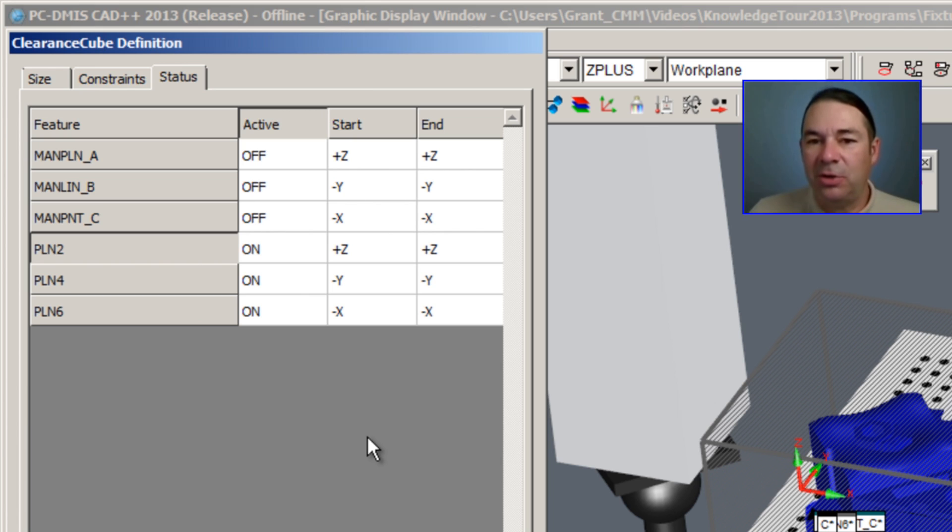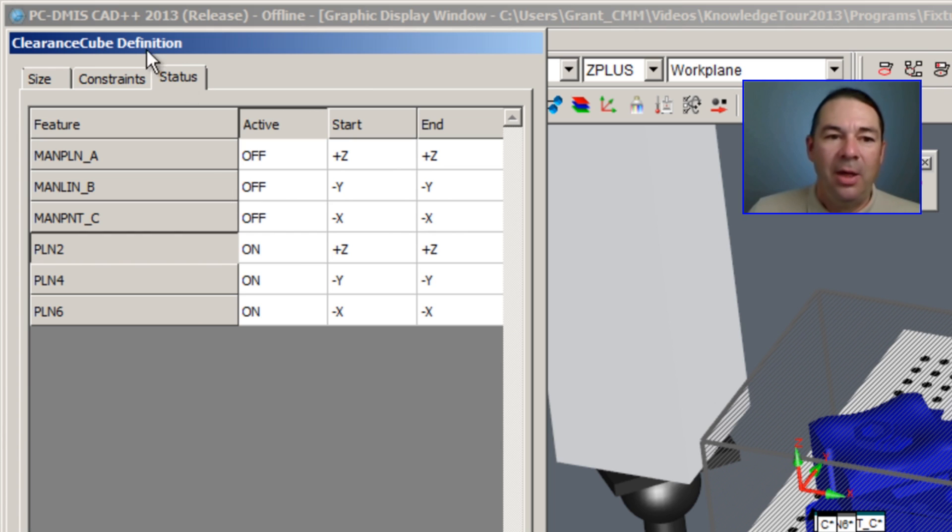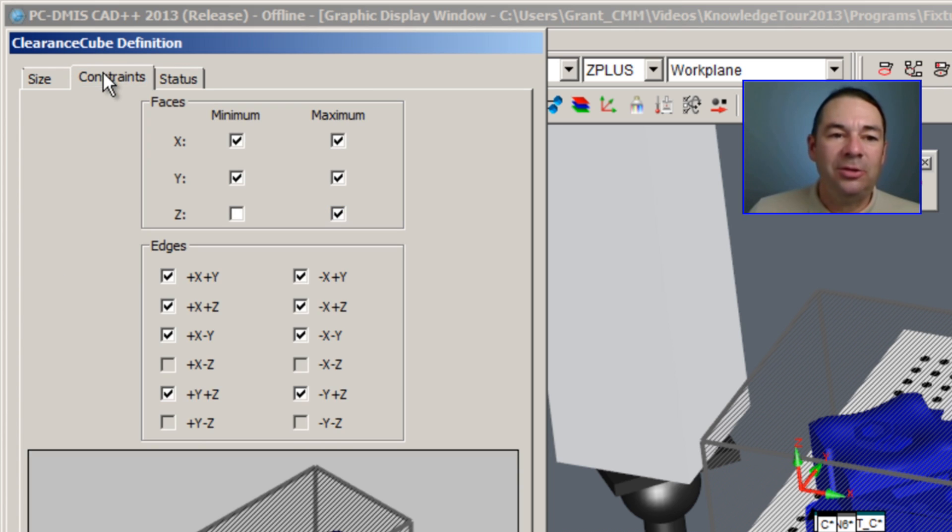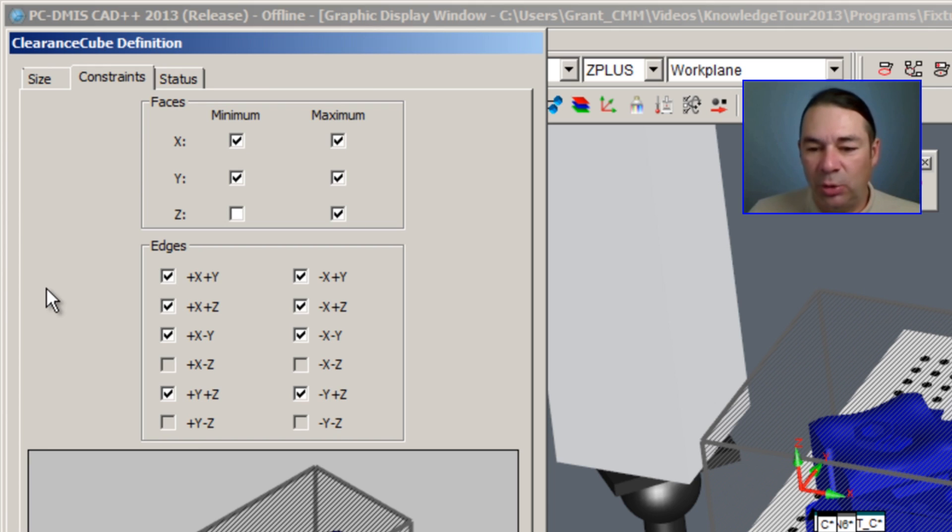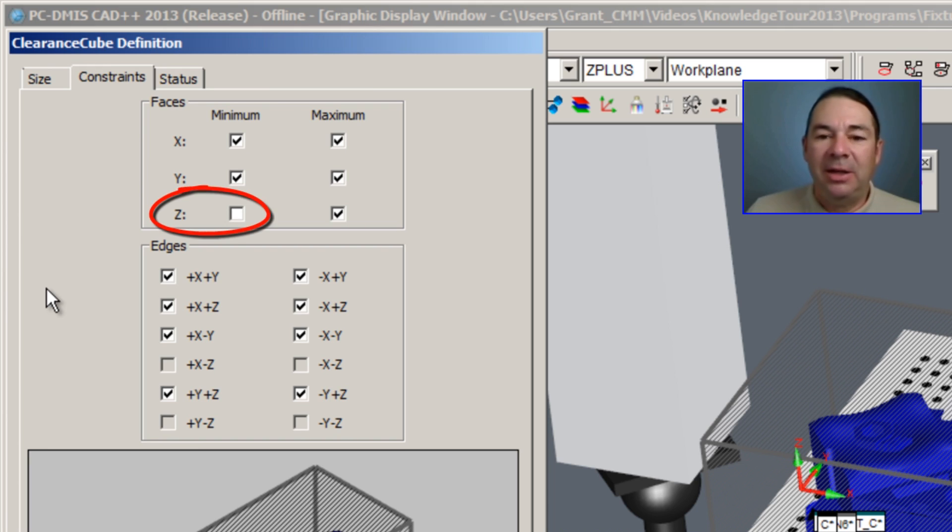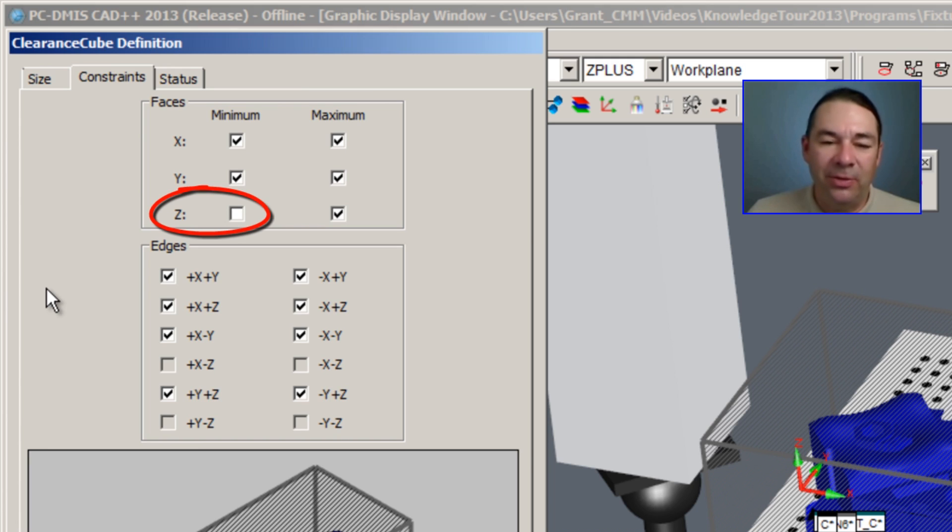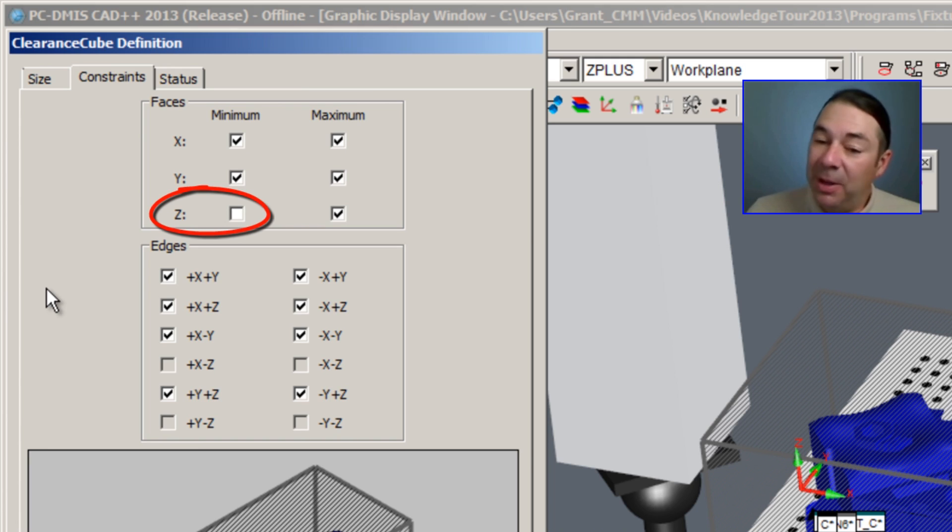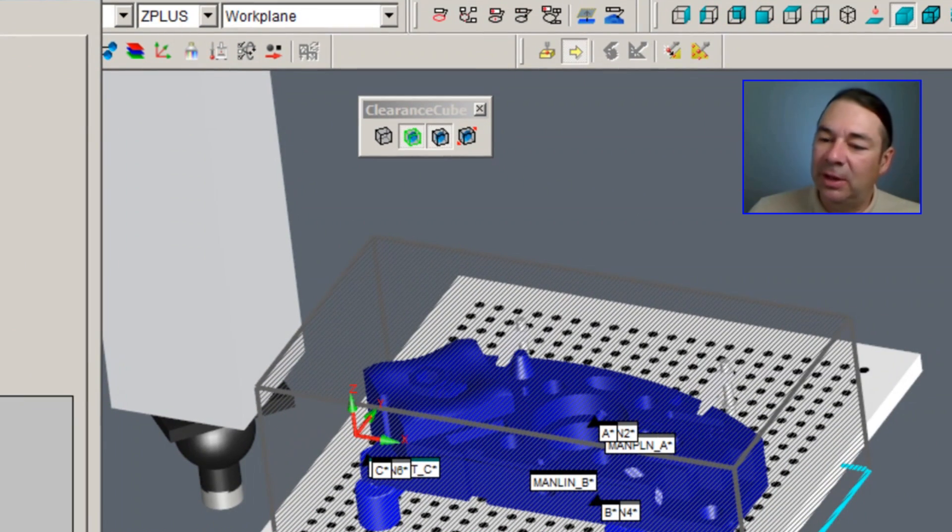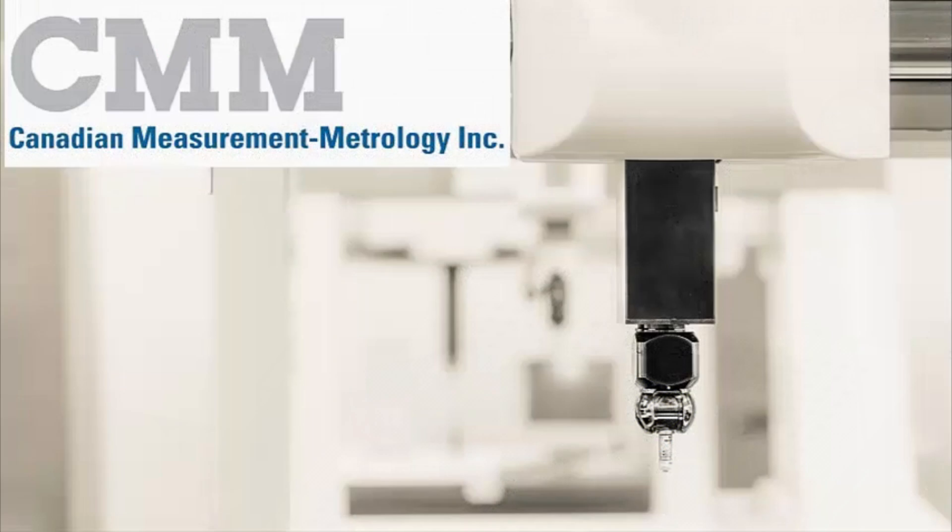The constraints dialog tells PC-DMIS which directions to apply the clearance cube in. By default, we've disabled the Z minimum direction because PC-DMIS knows if the part is sitting on a fixture not to drive clear in the Z minus direction.